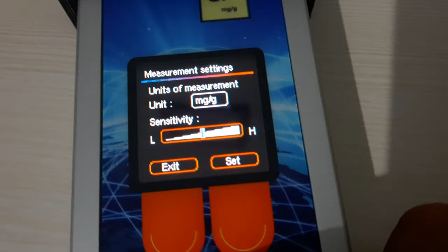Let us test it with the vial. 1.63. So again, we have to calibrate this device. Menu, then we will go to sensor settings, enter. First we will try to enter the calibration data. For the slope we will enter 68, and the next offset would be 0, set, and again let us exit and try to measure the data first. Again it is giving minus 0.007, so it has increased.